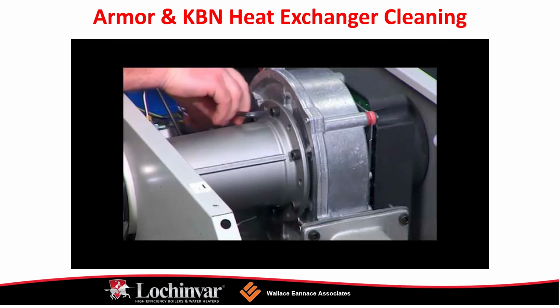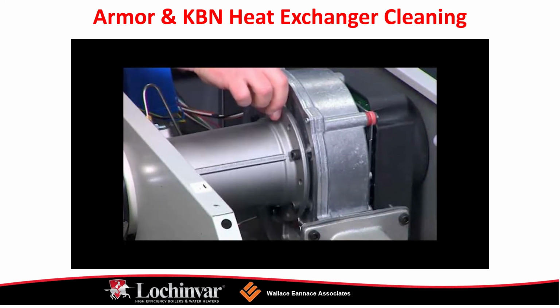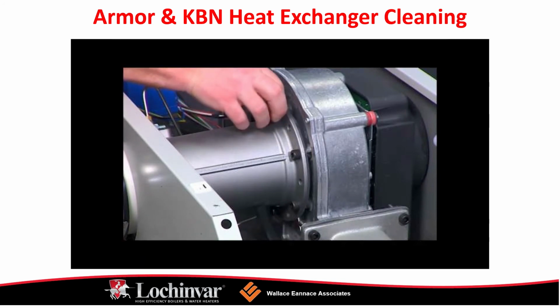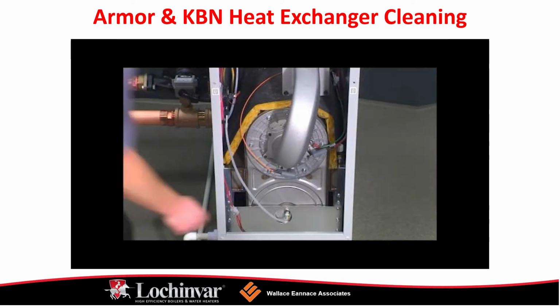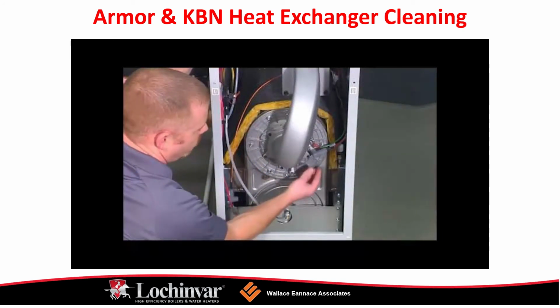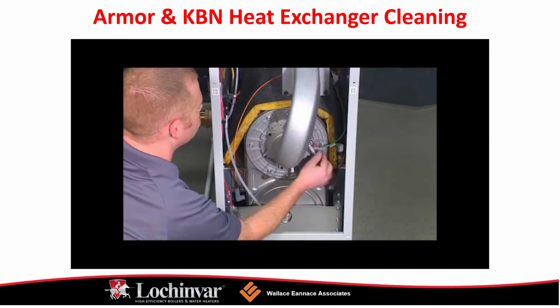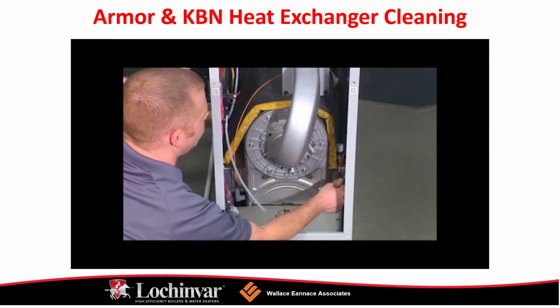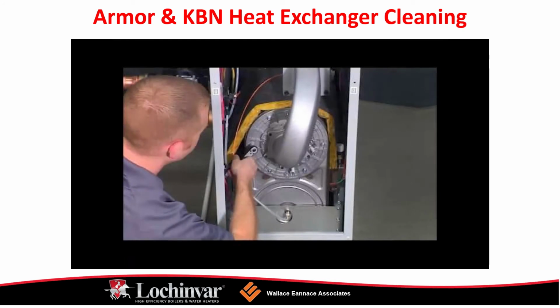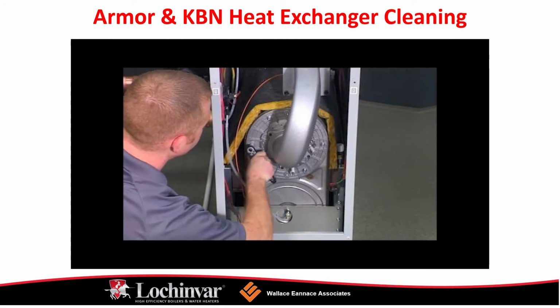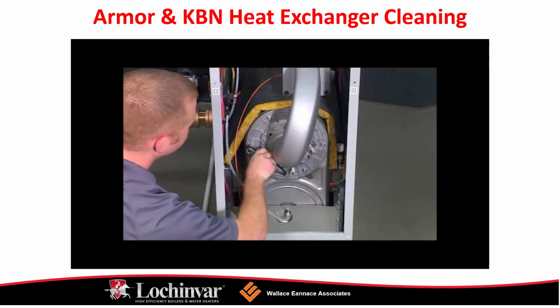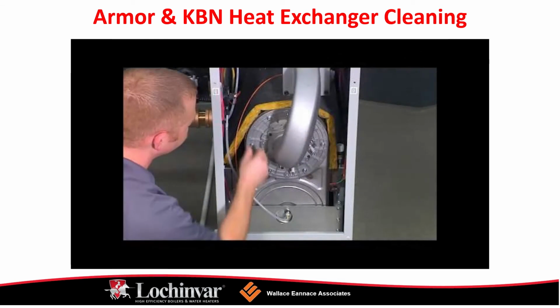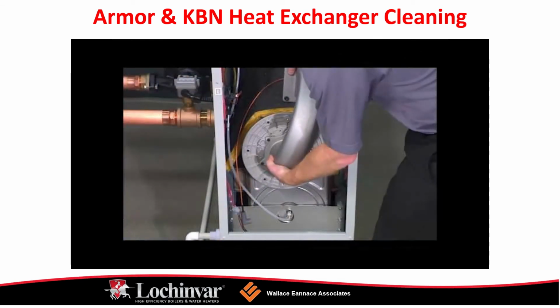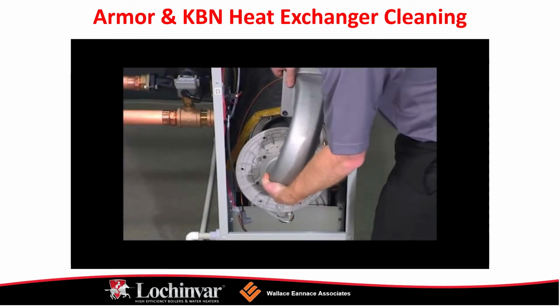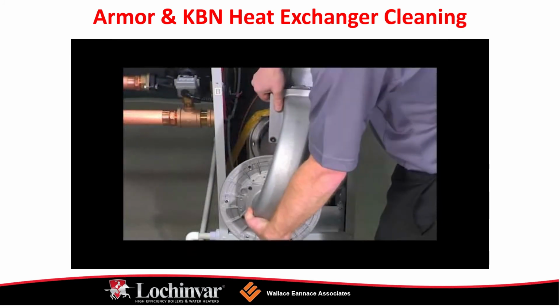Locate and disconnect the 2 wiring harness connections on the combustion blower. For 151 through 286 models, use a 4mm Allen wrench to remove the screws securing the gas valve Venturi to the inlet of the combustion blower. For 400 models, use a 5mm Allen wrench to remove the screws securing the gas valve Venturi to the inlet of the combustion blower.